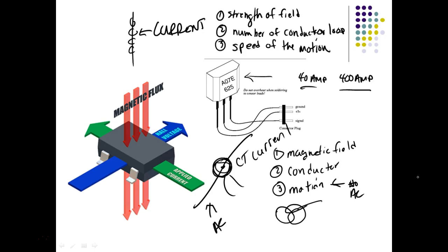You understand? So now you can measure 20 amps reliably by looping it what? But if you loop it twice, if it says 40, it's actually what? 20. If you loop it 3 times, then, so that's a trick that you can measure lower currents with a clamp-on ammeter just by doing what? Looping the conductor in the same direction, by the way. Okay, guys, I'll take a break and then I'll wire up a.